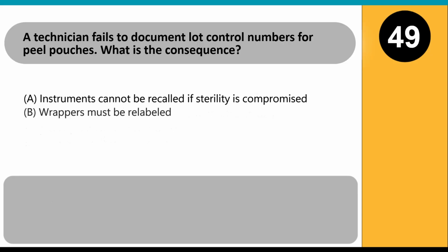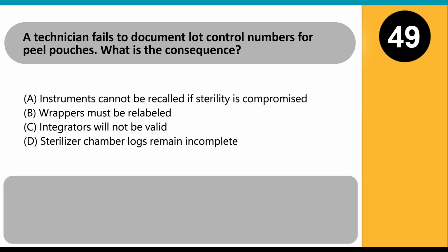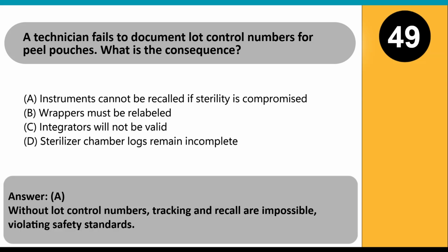A technician fails to document lot control numbers for peel pouches. What is the consequence? A. Instruments cannot be recalled if sterility is compromised. B. Wrappers must be relabeled. C. Integrators will not be valid. D. Sterilizer chamber logs remain incomplete. Answer: A. Without lot control numbers, tracking and recall are impossible, violating safety standards.